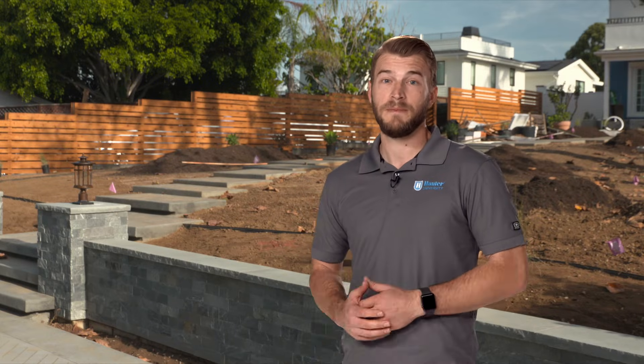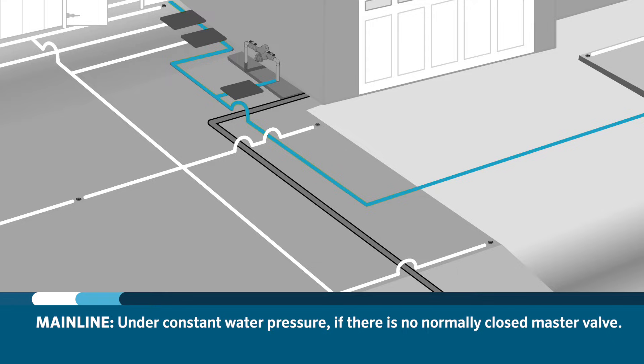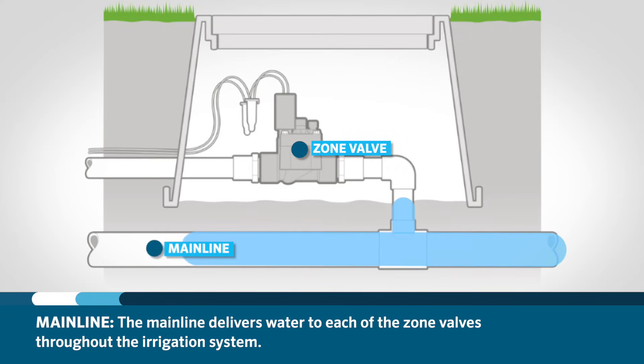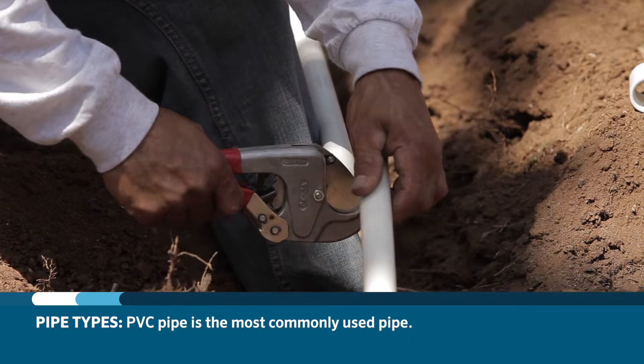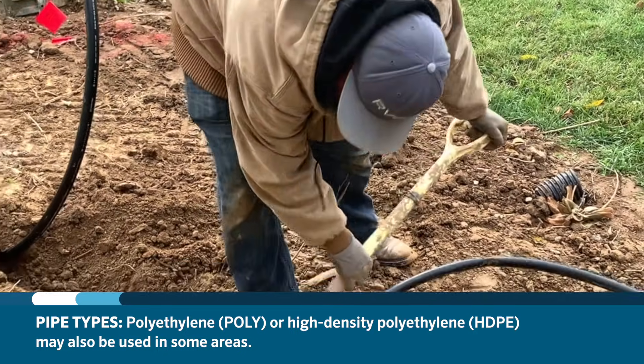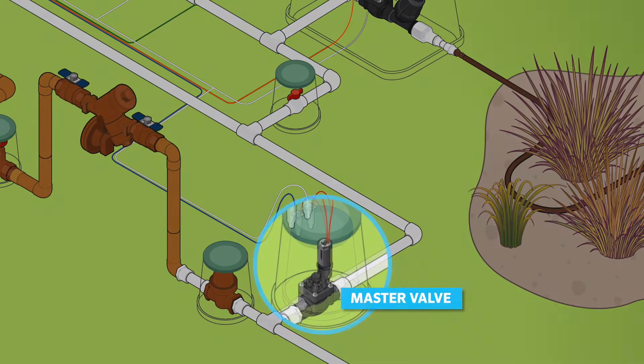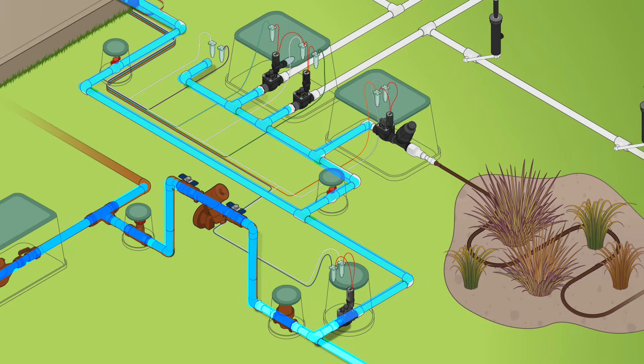Downstream of the master valve and flow sensor is the sprinkler mainline — the largest pipe in the irrigation system. If there is no master valve, this pipe is typically under constant water pressure at all times, 24/7. The mainline delivers water to each of the zone valves throughout the irrigation system. PVC pipe is the most commonly used pipe for this, but in some areas polyethylene, also known as poly, or high-density polyethylene or HDPE might be used. If a normally closed master valve is installed, the mainline only remains under pressure during scheduled irrigation cycles.